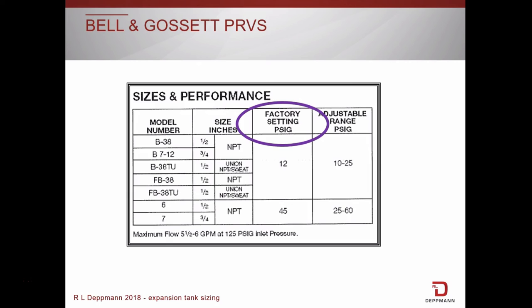Watch your specifications. The Bell & Gossett PRV model B7-12 shown here has an adjustable range of 10 to 25 psig. The model number 7 has an adjustable range of 25 to 60 psig. We also have others for higher fill pressures.